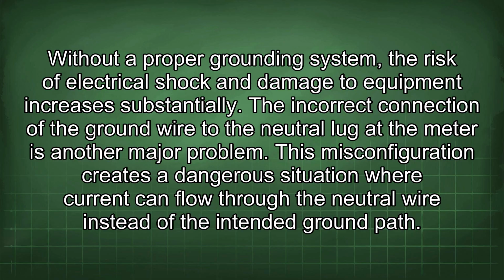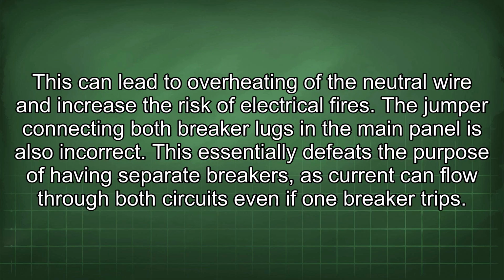The incorrect connection of the ground wire to the neutral lug at the meter is another major problem. This misconfiguration creates a dangerous situation where current can flow through the neutral wire instead of the intended ground path. This can lead to overheating of the neutral wire and increase the risk of electrical fires.